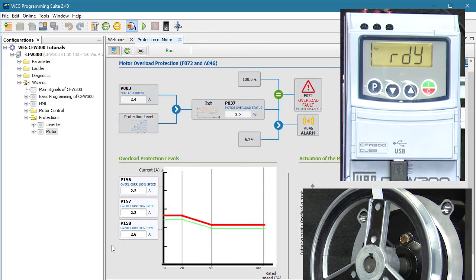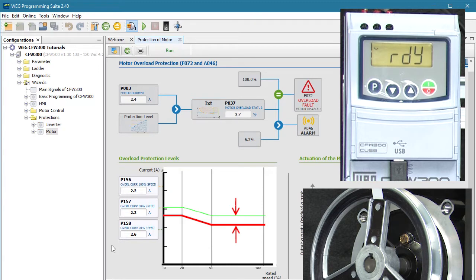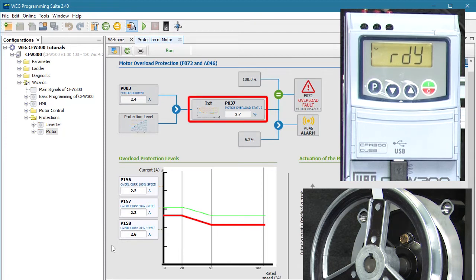So now if we were to add some load to my motor and the current rose above this curve, the IXT function would take the amount the overloaded motor current exceeded the curve that we created and add it to the previous amount. It will keep doing this over and over again as time goes on — if the motor current stays above the line, that sum will grow or integrate.